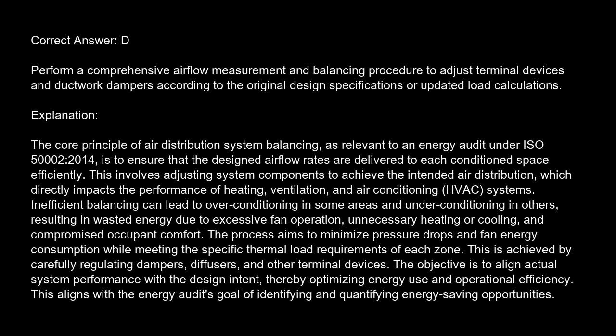energy due to excessive fan operation, unnecessary heating or cooling, and compromised occupant comfort. The process aims to minimize pressure drops and fan energy consumption, while meeting the specific thermal load requirements of each zone. This is achieved by carefully regulating dampers, diffusers, and other terminal devices. The objective is to align actual system performance with the design intent, thereby optimizing energy use and operational efficiency. This aligns with the energy audit's goal of identifying and quantifying energy-saving opportunities.